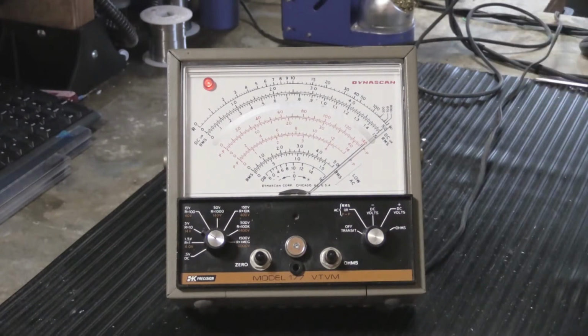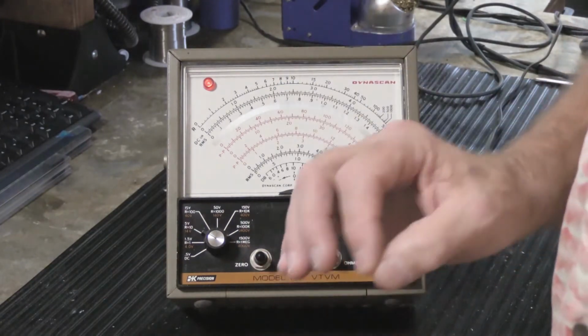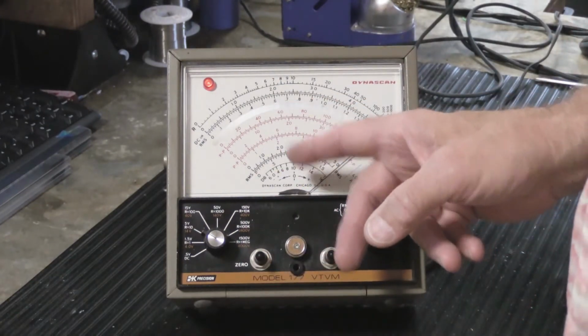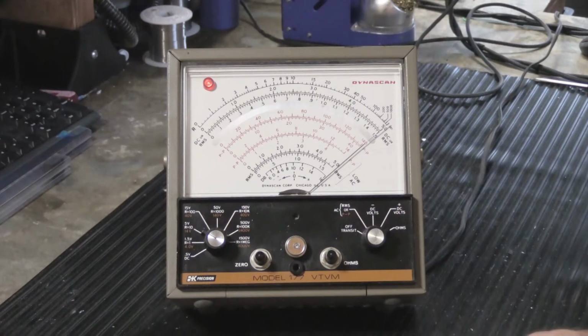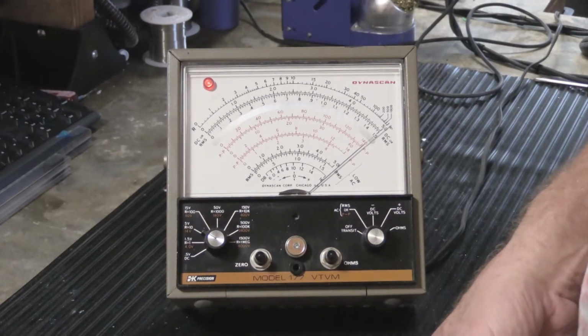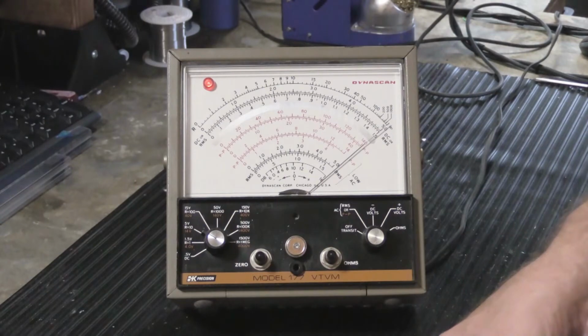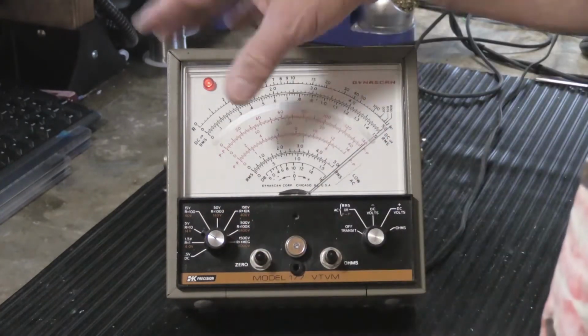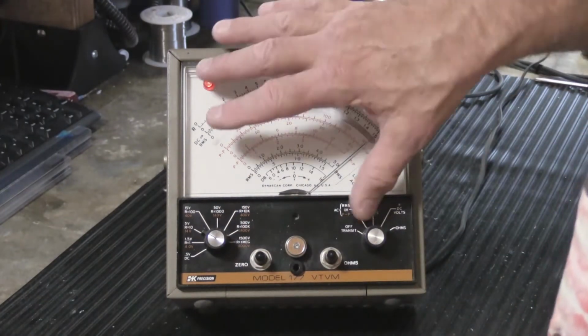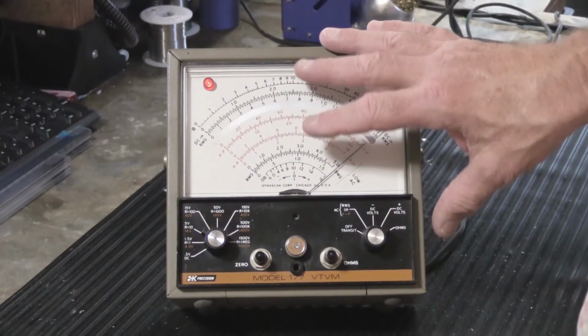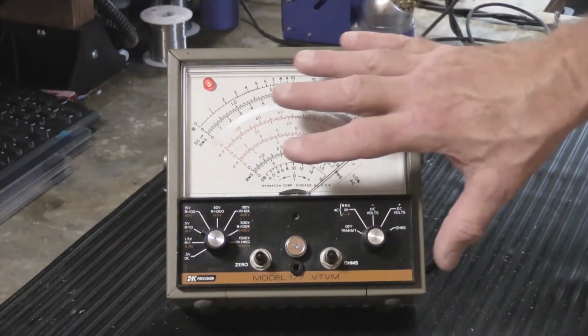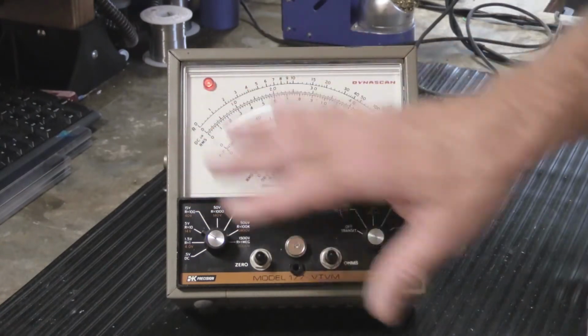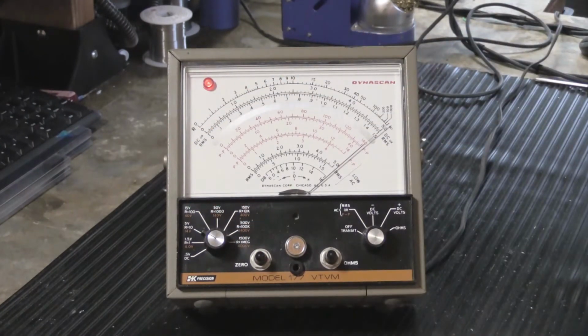However, if you want your readings to be as accurate as possible for a meter of this type, and we'll talk about accuracy in a minute, you should turn it on well ahead of the time you're actually going to use it and leave it turned on, because the vacuum tube is going to generate heat inside the metal case, and that heat will affect other components in here. And what you really want to have happen is have it left turned on long enough, maybe 20 or 30 minutes, so all the temperatures inside the case are equalized and it won't drift as it warms up more and more. And you certainly don't want to be turning it off and on and off and on, because that's just annoying.